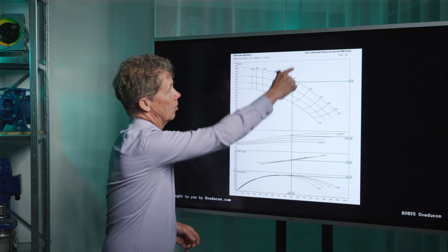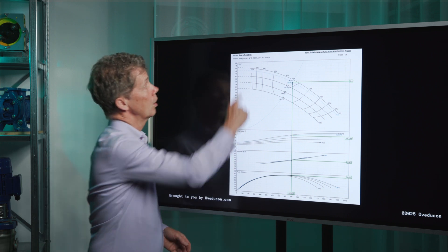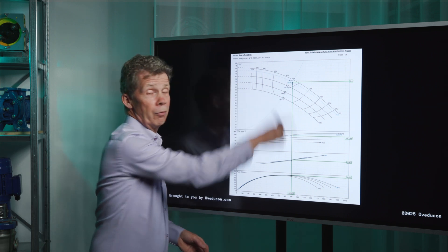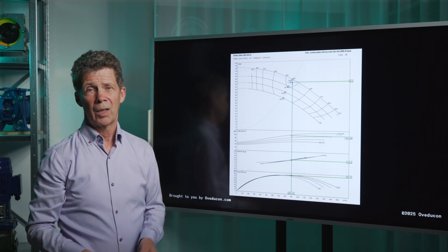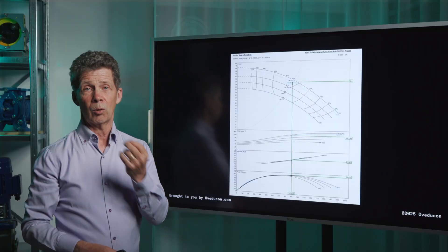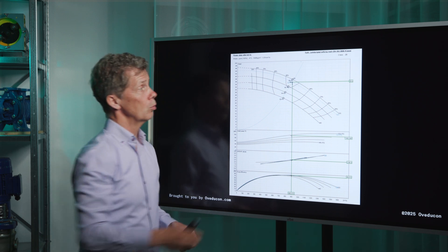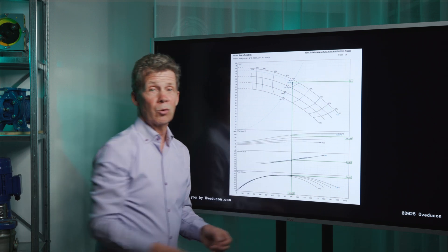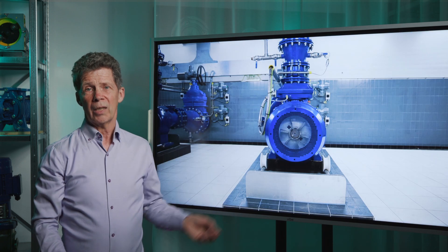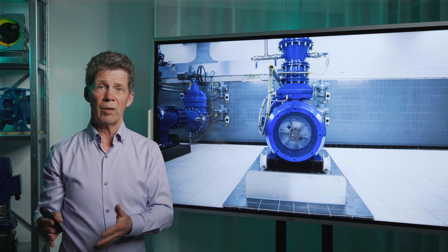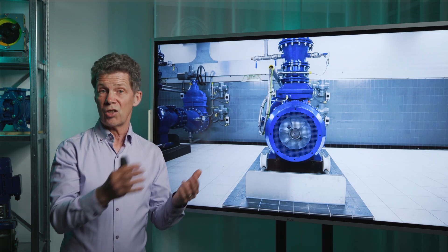This is the line of your system — your system curve — and here you see different pump curve lines. And on the point where your system curve intersects your pump curve, that will be your operating point. On that point you know your pump will do this amount of flow and this amount of head. And if you know that, you also know if your pump is running at the desired parameters and also with the desired efficiency.